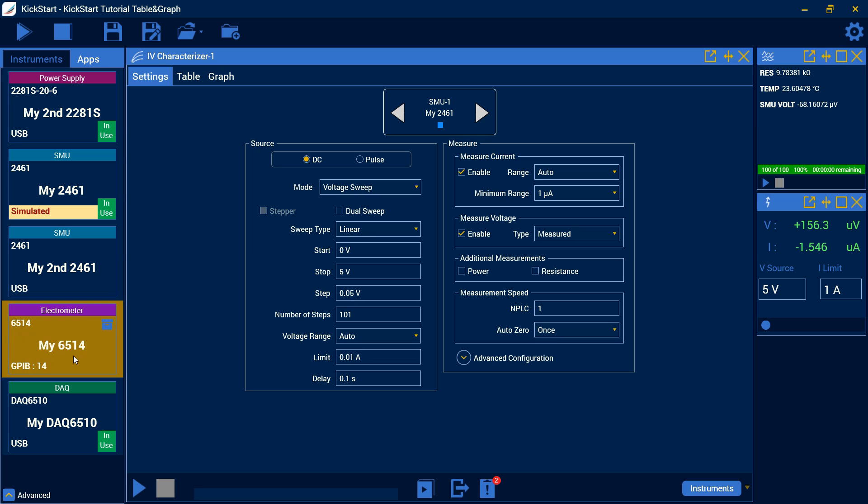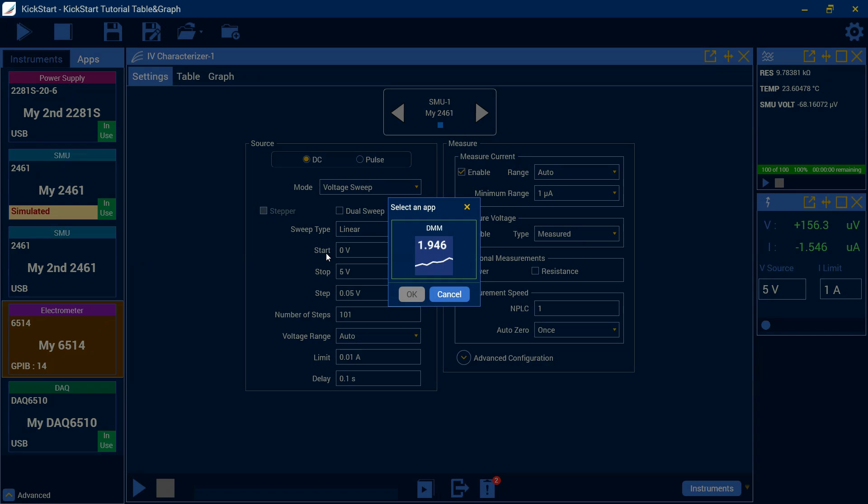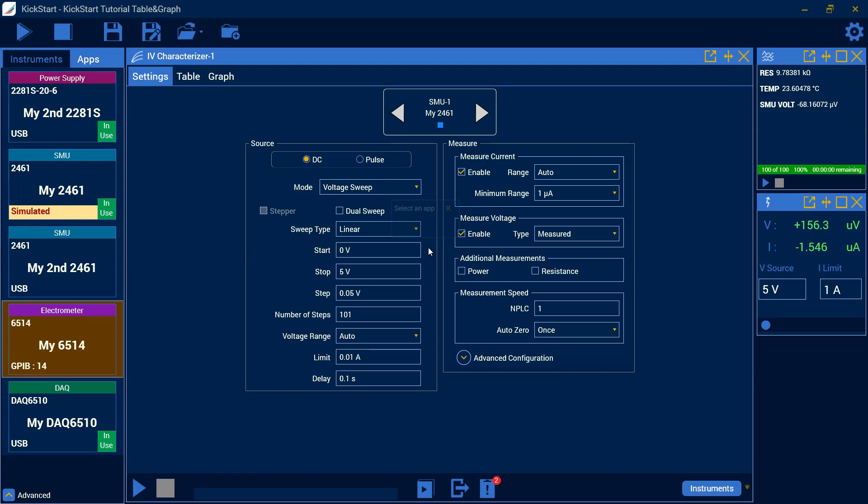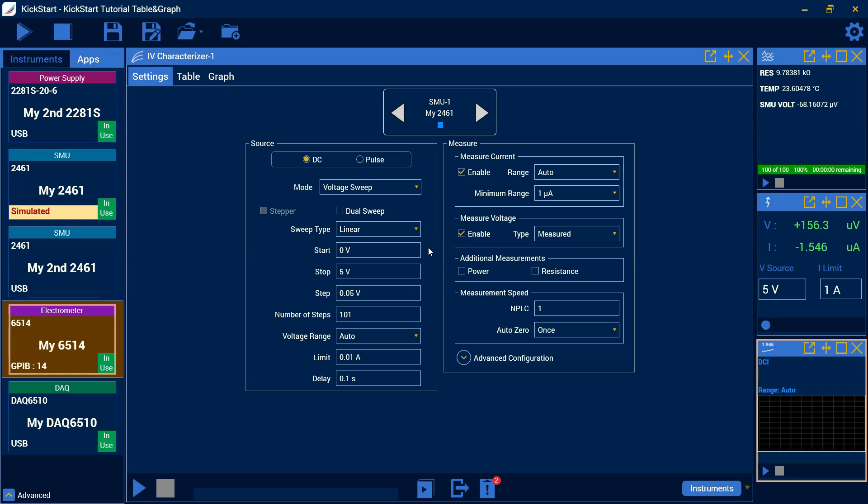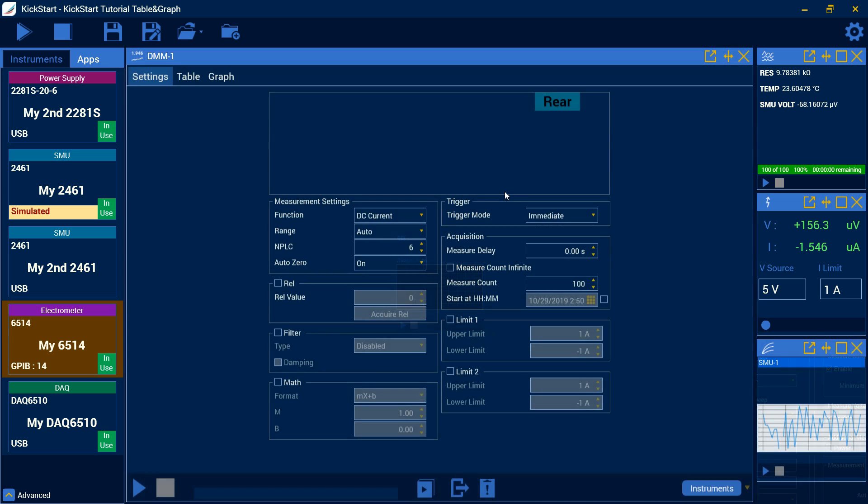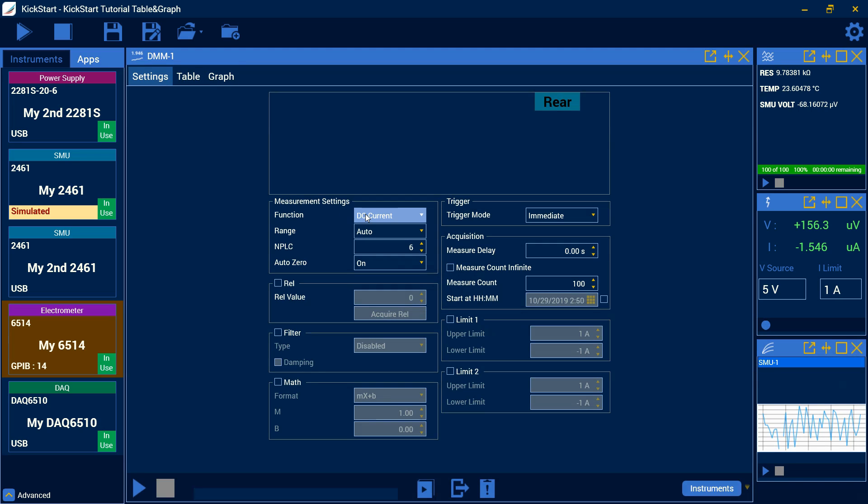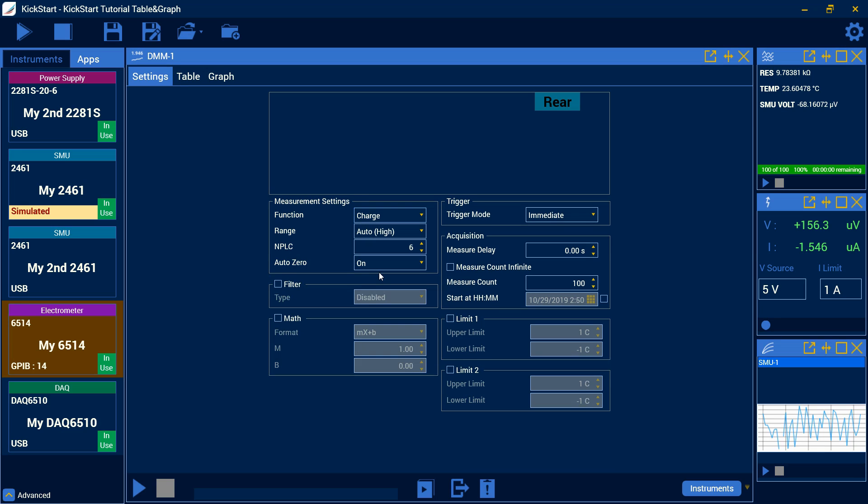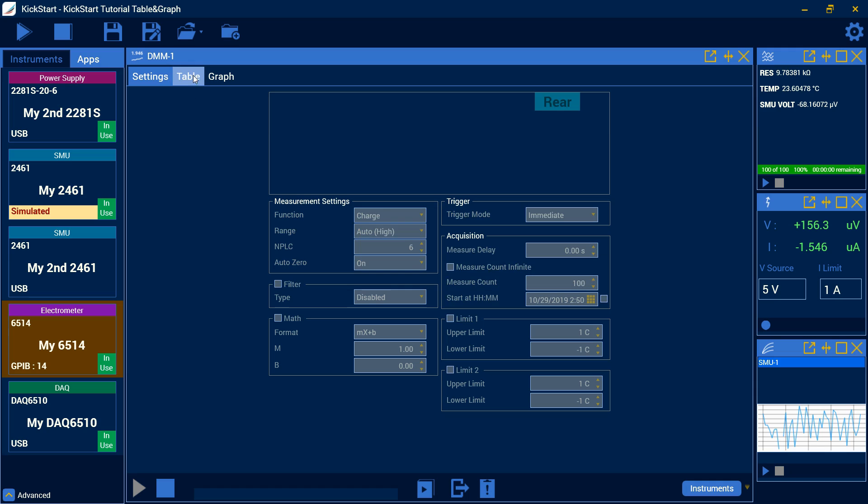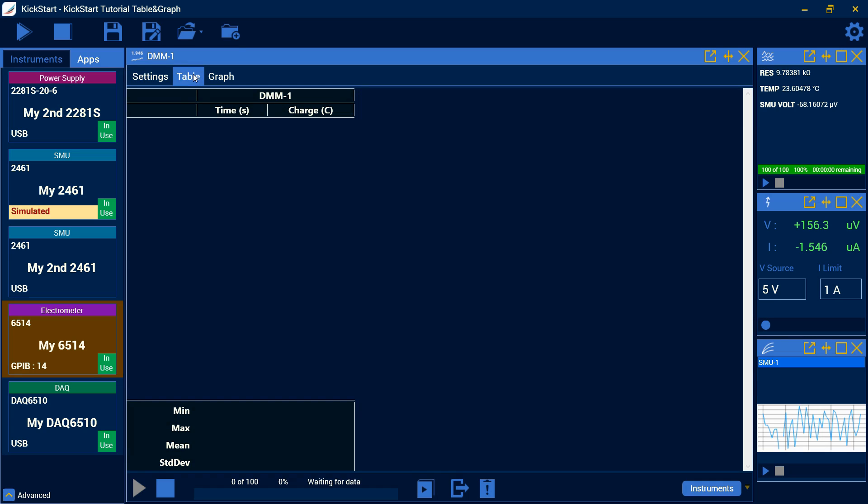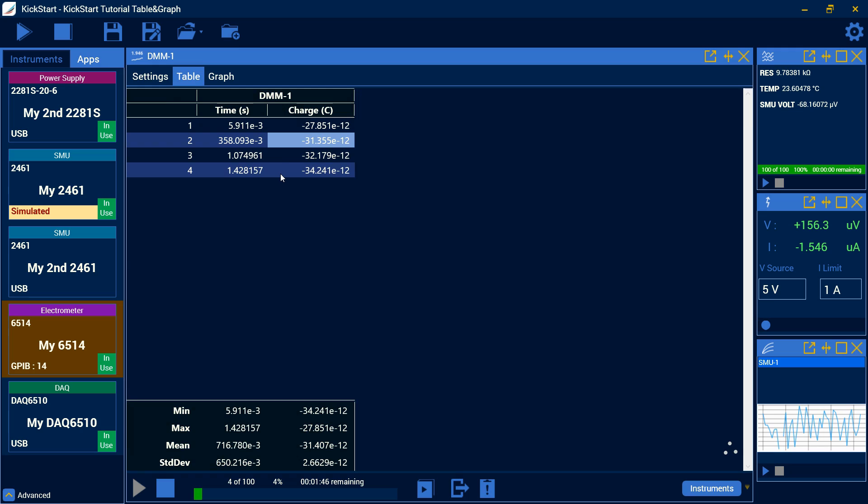Right now, I'm going to hook up our 6514 and I'm going to open it up in the DMM app. I'm going to maximize our 6514 and we're going to take a look at some of the new functionality, which is in this DMM app with this electrometer, we can choose the charge function. I'm going to use the automatic settings. We can hit run. And as you can see, it's going to take a moment and we're starting to take data.